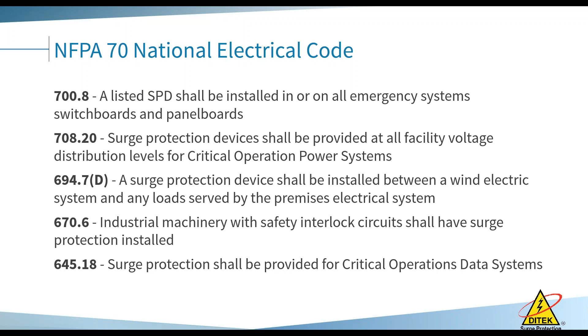When you talk about the 2020 edition now, any services supplying a dwelling have to have SPDs. So in the past, again, it was, the right thing to do is probably throw one on. Well, now all your new construction shall have one of these on here. The SPD has to be part of the service equipment or immediately adjacent to it, and then it must be Type 1 or 2. Real quick little synopsis of Type 1 and 2. People who've been around a bit, the Type 1 used to be called the arrestor, and goes on the line side. Type 2 used to be like a TVSS on the load side, but we'll get into that in a couple slides. Now we'll call it SPDs.